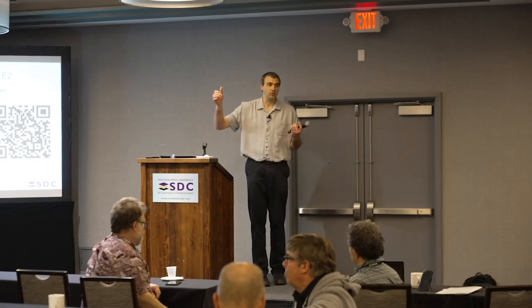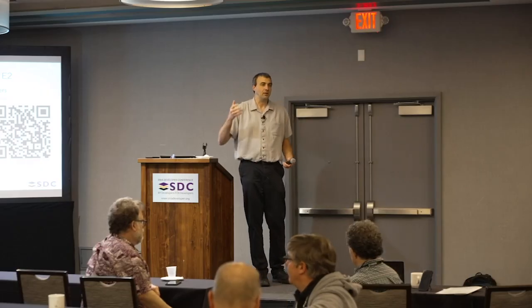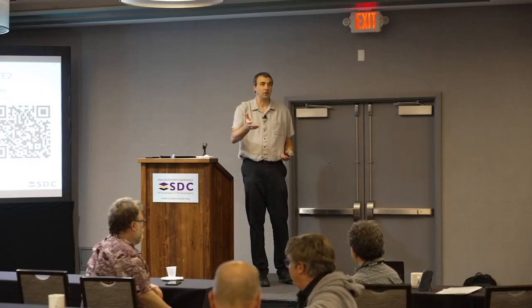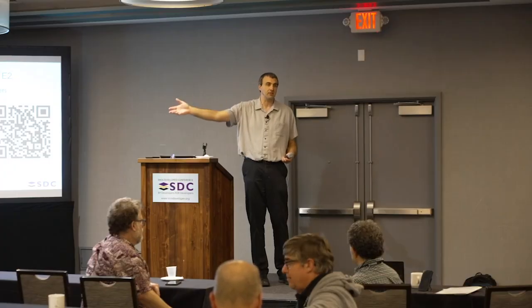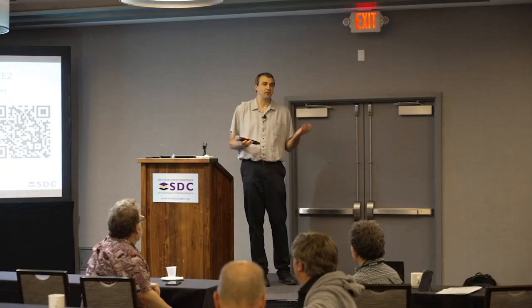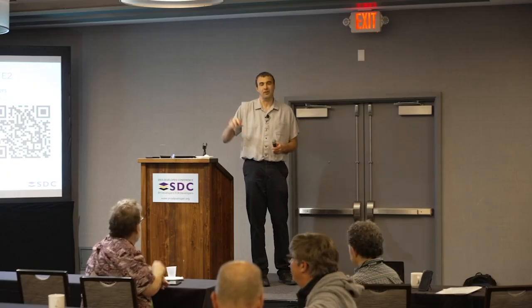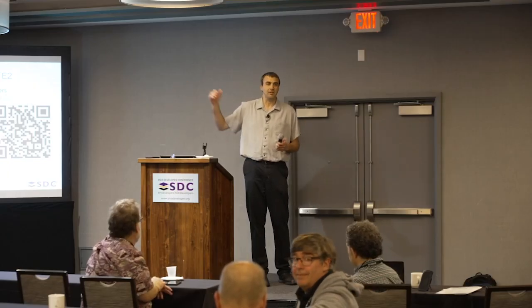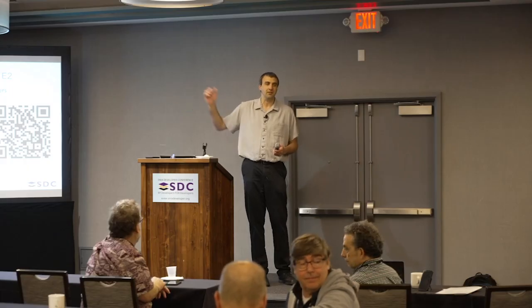This is the discussion when we get into liquid cooling, where you have a hot side. If you're going to do a single-sided cold plate, you have a hot side and a cold side, a side that you're going to want to hit the cold plate with. So we need to make sure we're all on the same page that this secondary side is real. We didn't have this defined for years for E1, but we figured it out because when we did the asymmetric design for E1.S, it made sense. But E1.L kind of didn't define it.